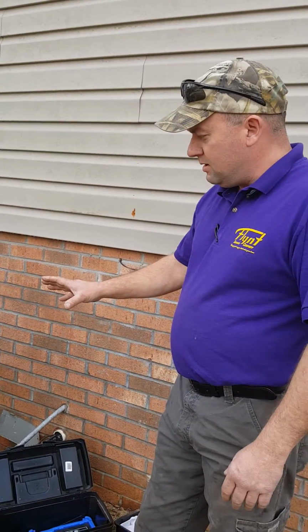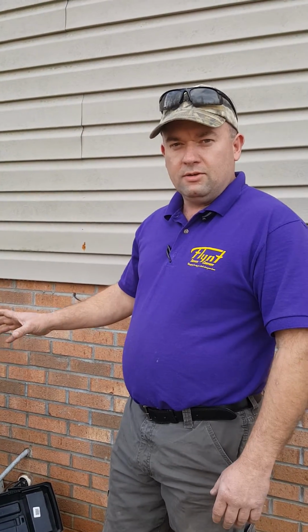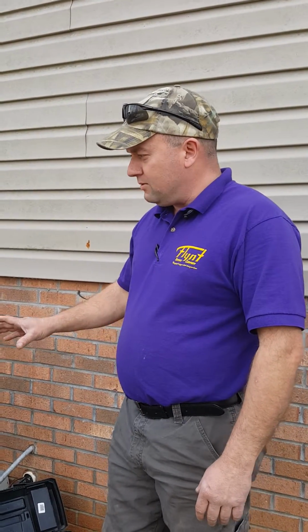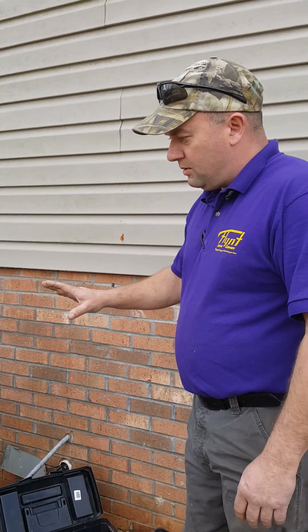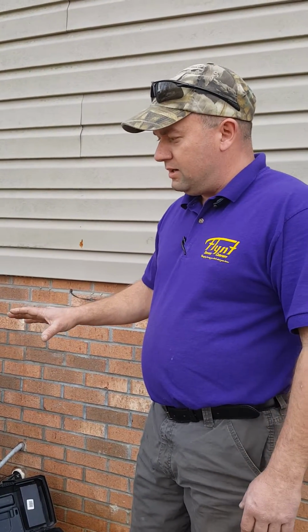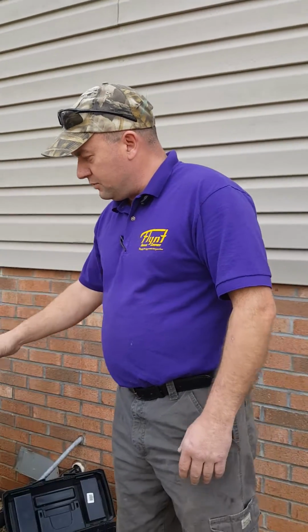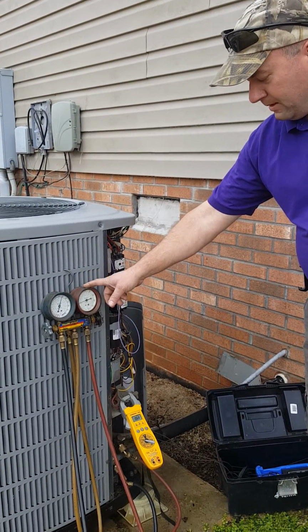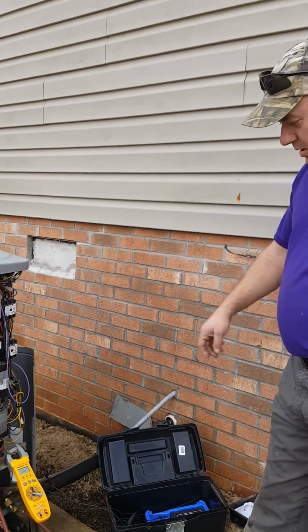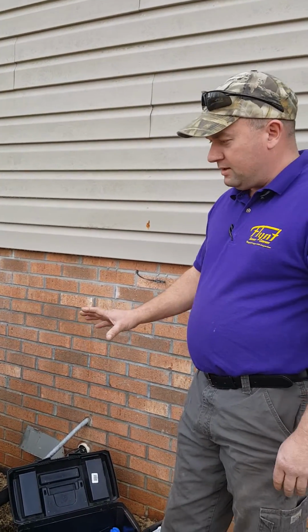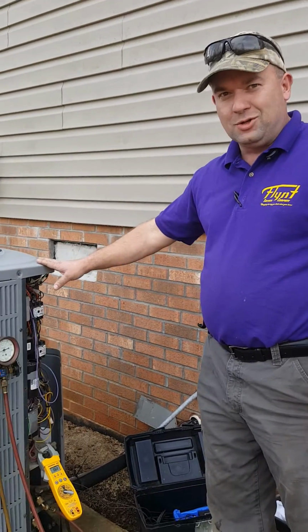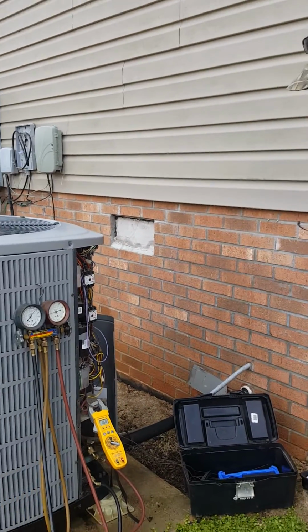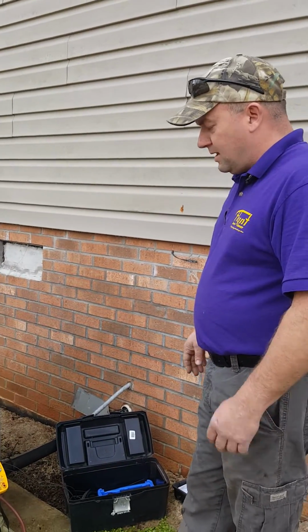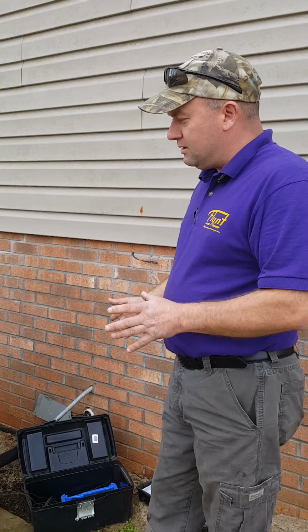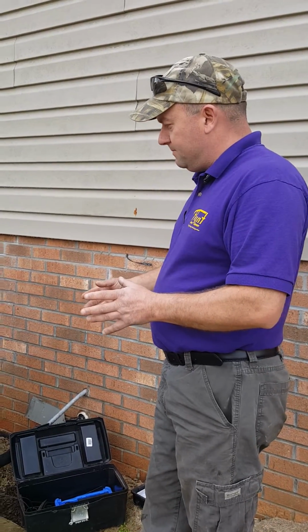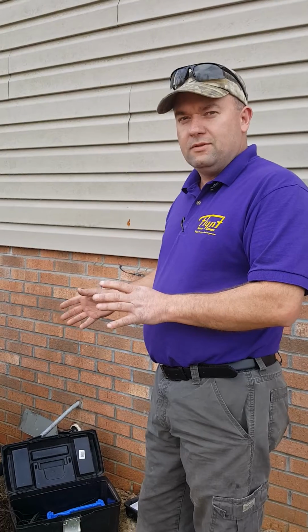All these units now come with a factory recommended charge, and that's what we will go by. This particular American Standard unit is required to be set at 11 degrees subcooling. That's just the difference of using the high pressure side and a temperature probe on the liquid line, and we do a little math to come up with that. You heard the click. This is a 2-stage unit, so it's getting ready to go into second gear. That's the basic steps we go through on the maintenance. Every unit's just a little bit different, so we tailor it to your specific system.